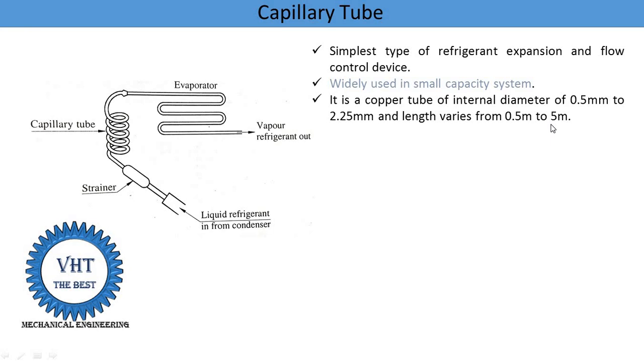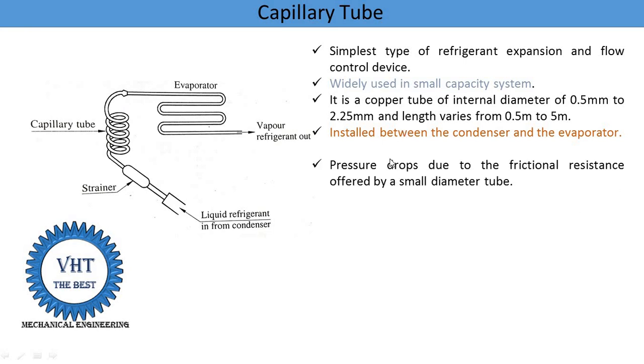According to different applications and the pressure requirement in the evaporator, we select a certain diameter and length of the tube. The capillary tube is installed between the condenser and evaporator in the liquid line. The pressure drop in the capillary tube occurs due to the frictional resistance offered by the small diameter tube. When refrigerant moves from a larger diameter tube into this smaller diameter capillary tube, frictional resistance causes the pressure to reduce.